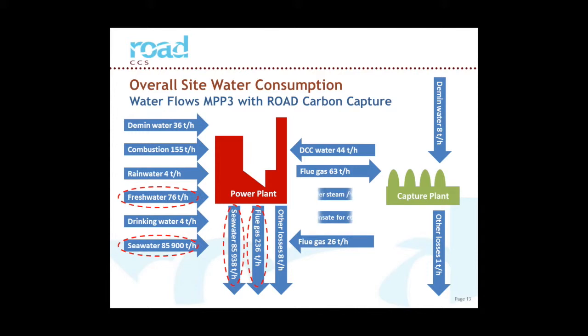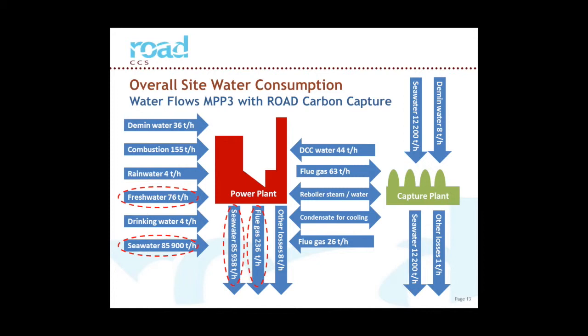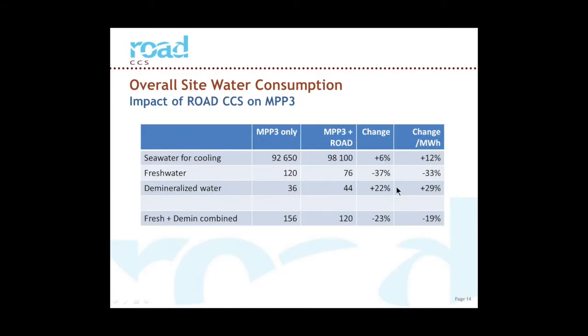If I go on to the next slide, this has got the boundaries on the totals for comparison in numbers, and you can see that the overall cooling water demand has increased. Although the cooling water demand for the power station has dropped, the overall number has increased. It's gone up by about 6%, and on a per megawatt basis that's about 12% because the capture plant has reduced the output overall by about 55 megawatts. Maybe 60 megawatts, depends on the load. And that's a combination of the effect of the steam offtake and the works power of the capture plant itself.